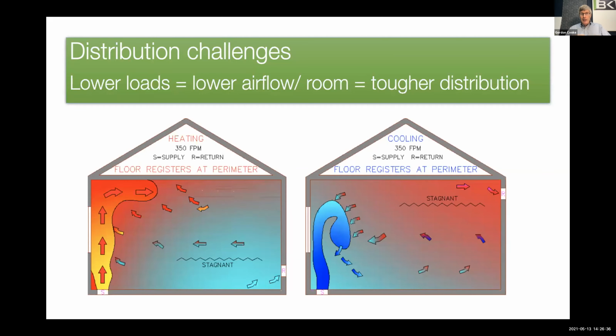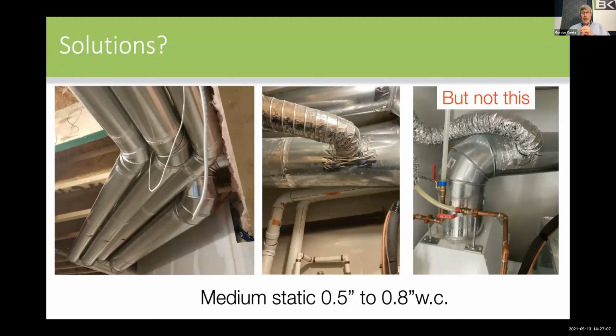And that whole idea of spread versus throw, I clearly have these slides out of order, but you'll notice this room on the right-hand side needs more throw. It needs the air to get up higher. It worked fine in winter because of the natural buoyancy of warm air, but in summer, that 350 feet per minute just isn't enough. I need to get to 550, 600, maybe 650 to get that throw up and over, or use a different grill, summer to winter, or an adjustable grill is what you want to get to. And I did mention, just in a few minutes remaining, that maybe we want to start designing for slightly higher static. Why do I say that? Because we now have furnaces with ECM motors that can get us a little higher static pressure, a little more oomph to get that air out to the room over the garage.